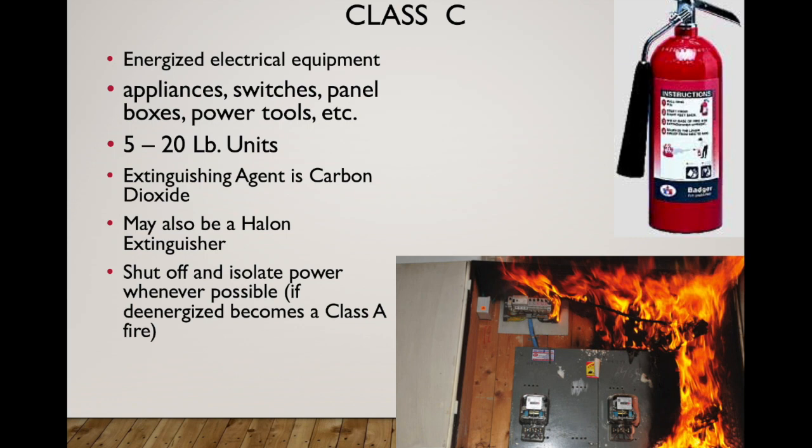Another important consideration with Class C energized electrical fires is whenever possible, if we can shut off the appliance or unit and isolate power to it and de-energize it, it becomes a Class A fire, and then we'd be able to use our water can or regular water. But it's important to determine whether we've actually been able to de-energize it and make sure that there's not some stored energy there.